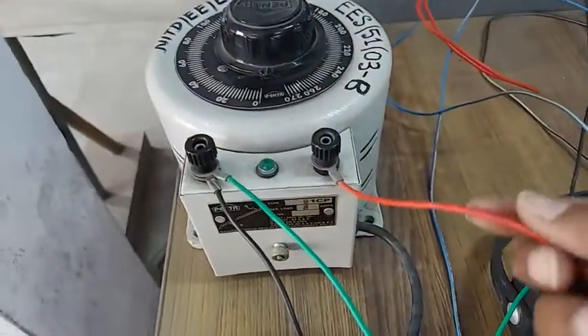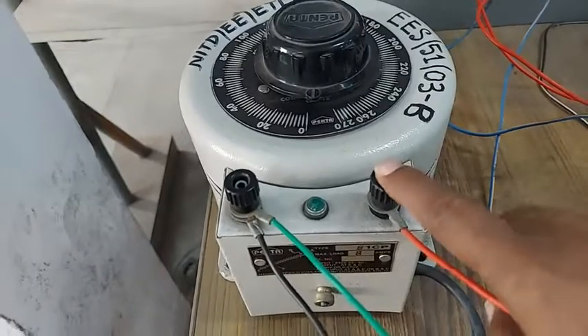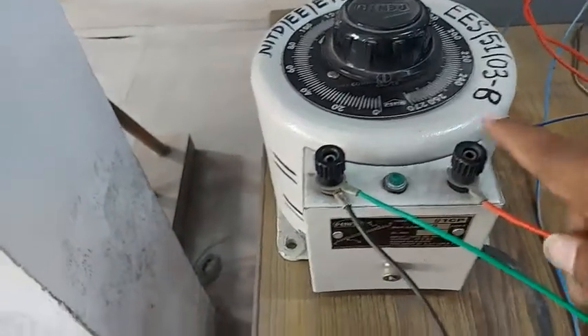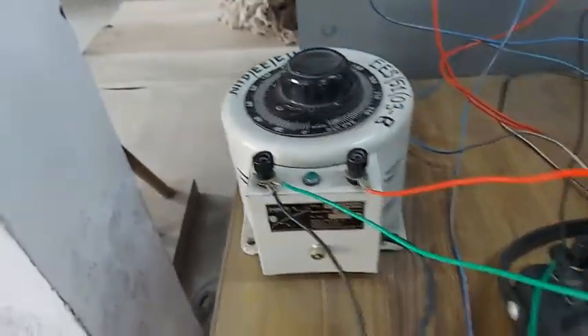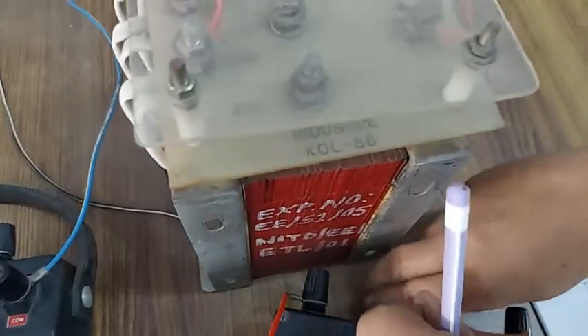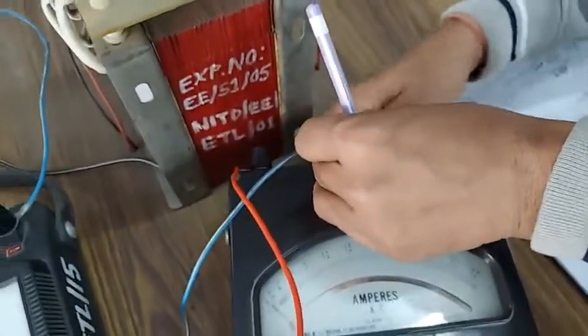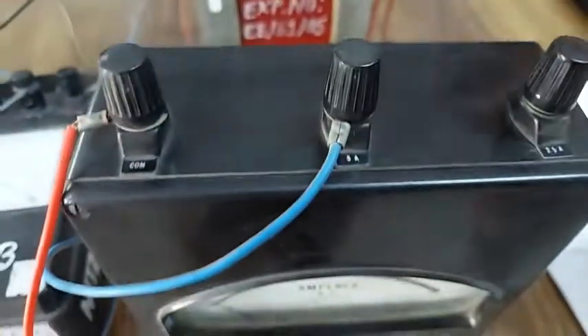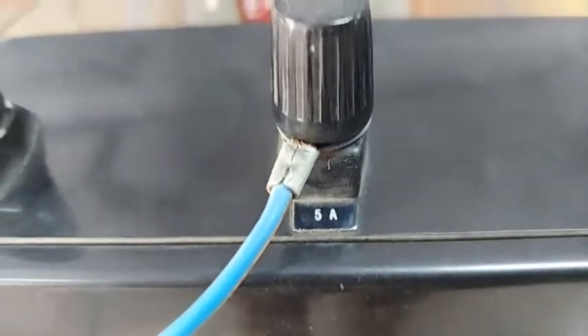Okay, after that we will get the ammeter connection. We will start from the positive terminal of the variac, this one is considered positive, though we can consider the other also, but here we have considered this one as positive. We will keep that in mind, and the red wire is going to the input of the ammeter, and that input of the ammeter will be connected to the common point, and after that the ammeter will be connected to the 5 ampere range, because the full load primary current will be approximately 4.5.